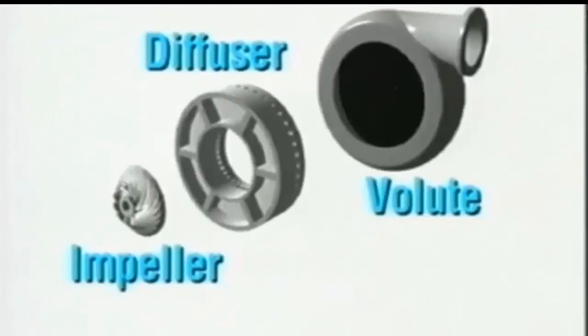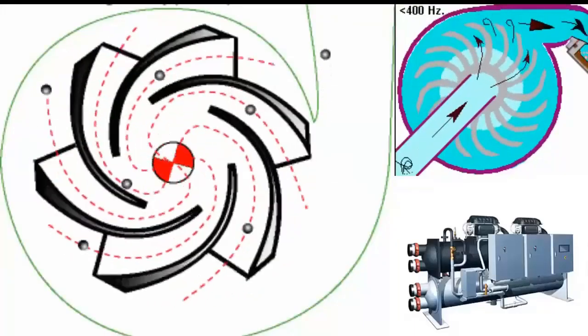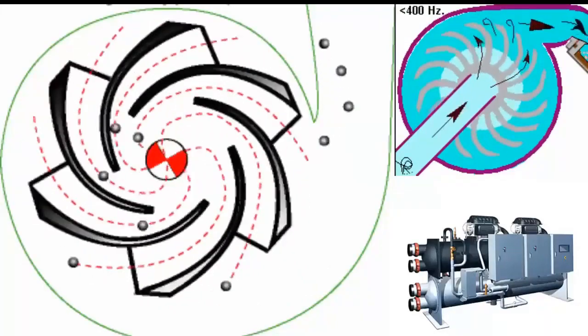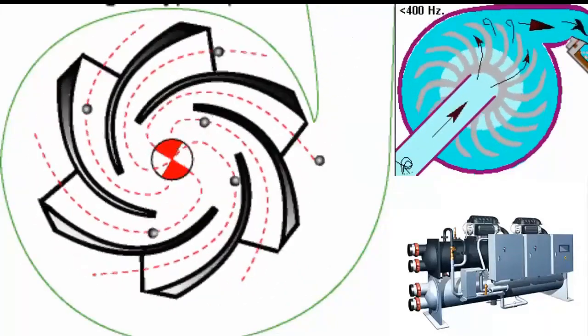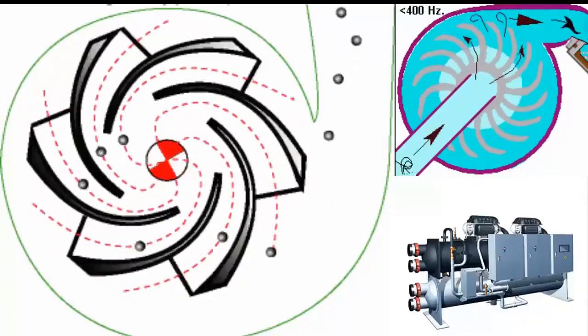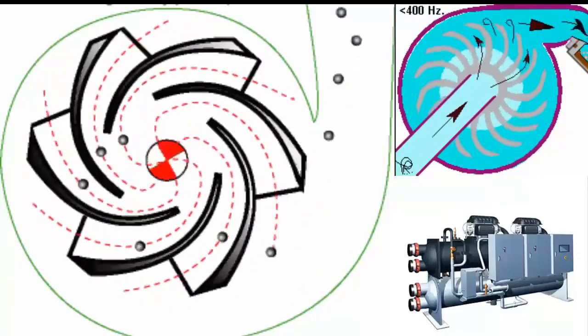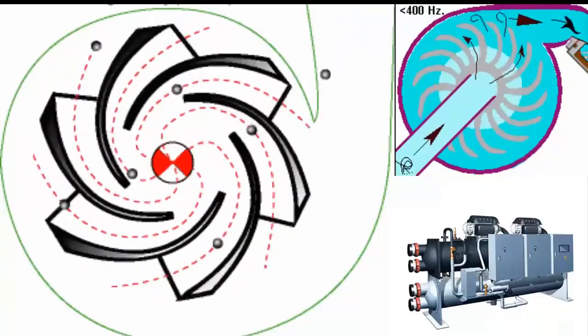When the coolant enters through the center and contacts the impellers it immediately picks up speed and acquires the velocity and properties of motion. The circumferential movement brings centrifugal force. This centrifugal force makes the refrigerant acquire a lot of speed, increasing the kinetic energy level. We are passing the energy that the compressor extracts from electricity to the refrigerant in the form of kinetic energy. But the refrigeration system does not need the refrigerant to have speed, it needs pressure, because the pressure is what will allow the compressor to make the refrigerant flow through the circuit and facilitate condensation in the condenser.